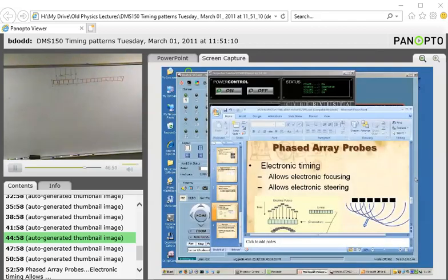Is the crystal a much bigger crystal on the single one than these are? Yeah, because for an abdominal scan, we're going to be scanning somewhere down at about 10 centimeters depth, right? So for 10 centimeters depth, we're going to need a crystal diameter of somewhere around 2 to 4 millimeters for a single crystal. And these little crystallets in a phased array are less than a millimeter. So you're going to have to use multiple crystals in order to get a focal zone down here at 10 centimeters.